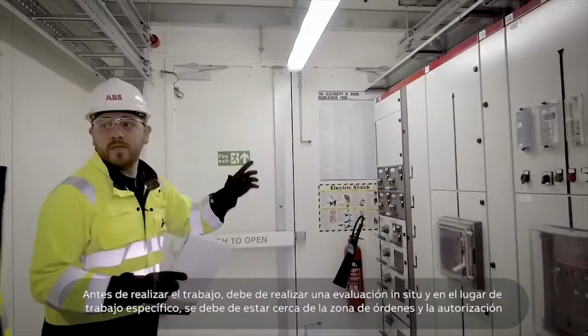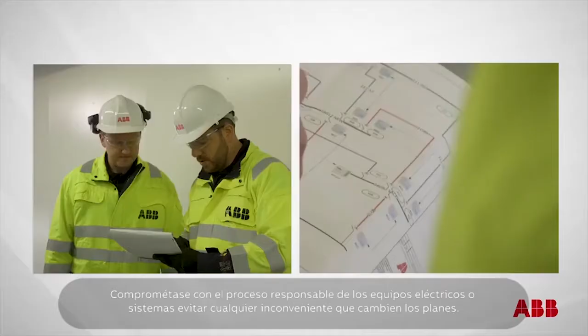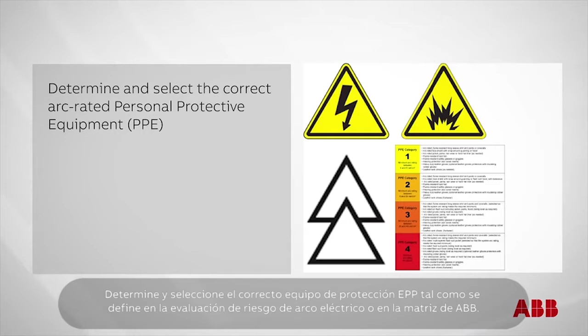Ensure the fitness and technical competence of workers. Check that they have the correct tools for the job and engage the person responsible for electrical equipment or system to review single-line diagrams, schematics, and switching plans. Determine and select the correct ARC-rated personal protective equipment (PPE) and associated PPE as defined in the Arc Flash Risk Assessment or ABB matrix.